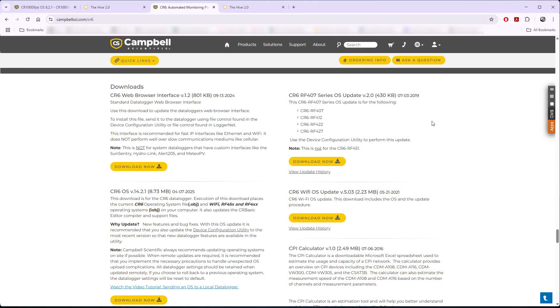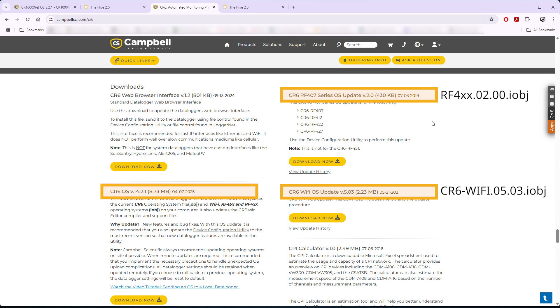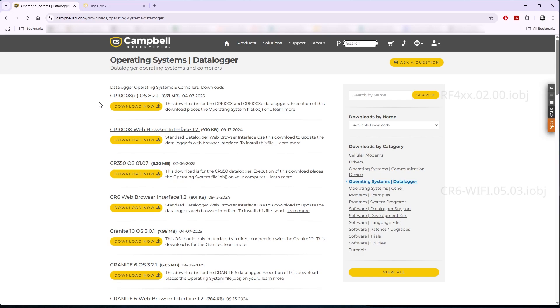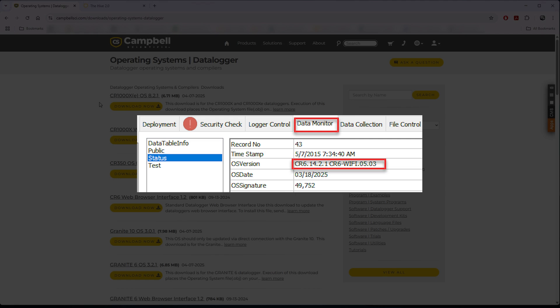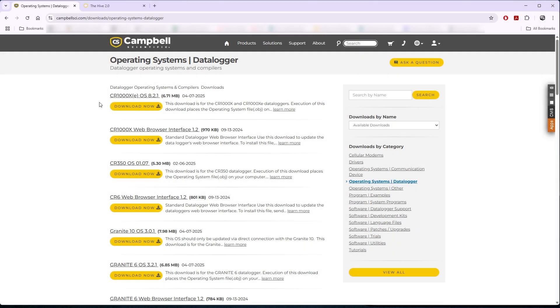If using a CR6 WiFi or CR6 RF400 series, the OS download will also include operating systems for the WiFi or radio data board, which are separate from the main data logger OS. These daughter board OSes have a .iobj extension. I can check if my data logger has the latest WiFi or radio operating system in the status table. The procedure for updating the .iobj files are included in the OS download.